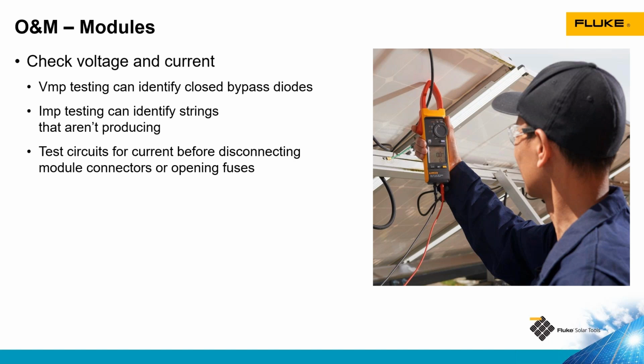If I should open one of those under load, it's going to arc between the terminals. It's going to cause damage to the terminals. It's going to be a hazard for the technician as well.